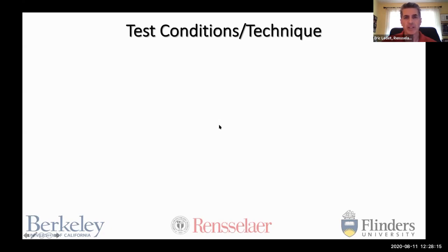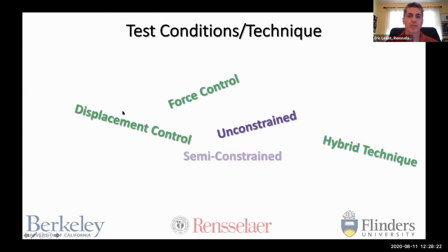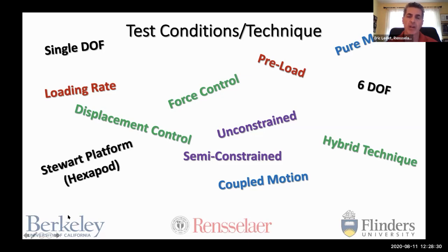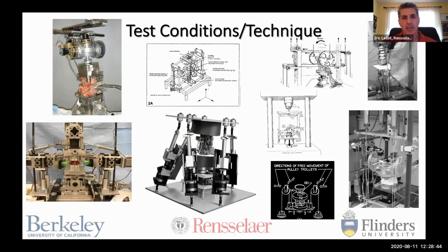Looking at the details of test conditions and testing technique, there are many different parameters: force control, displacement control, or a hybrid technique; testing unconstrained versus semi-constrained; coupled motion versus pure moments; what loading rates are appropriate; single degree of freedom versus six degrees of freedom; and what type of actuator is used. A lot of different systems have been described, with claims of pure moments and unconstrained testing — but if one looks very closely at some systems, it's not always necessarily the case. One reason why this is so hard and why everybody does it so differently is that in vivo moments are generally unknown. In vivo motions are measurable, but reproducing that from a volunteer in a cadaveric specimen can create some disconnect.